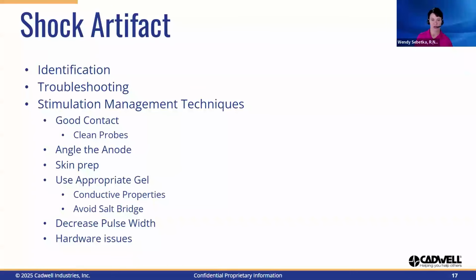Eliminating shock artifact is generally done by using proper stimulation techniques. These include properly cleaning the stim probe to prevent buildup of excess gel, applying firm, steady pressure, properly prepping the skin and removing any moisture or debris, and using appropriate amounts of conductive gel, making sure not to create a salt bridge. Decreasing the pulse width of the stimulus and slightly angling the anode may be a beneficial technique in swinging the baseline and improving the response. In rare cases, a failing stim controller or e-stim controller may cause this issue.